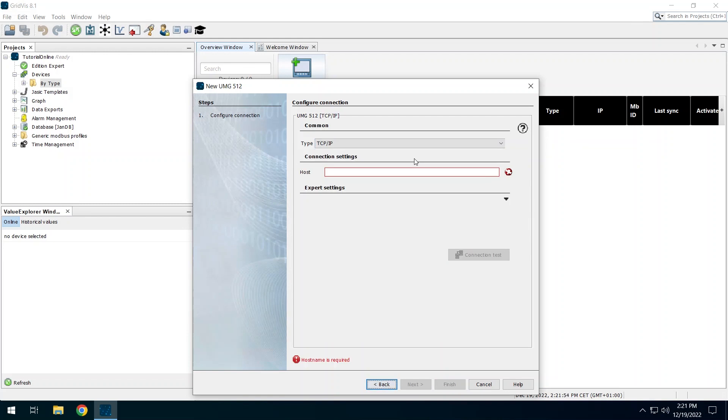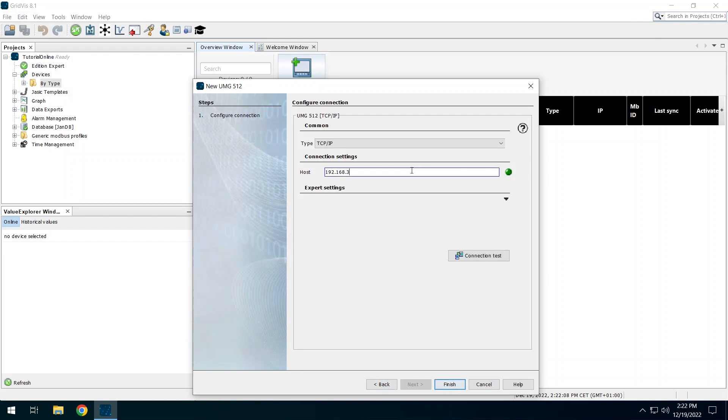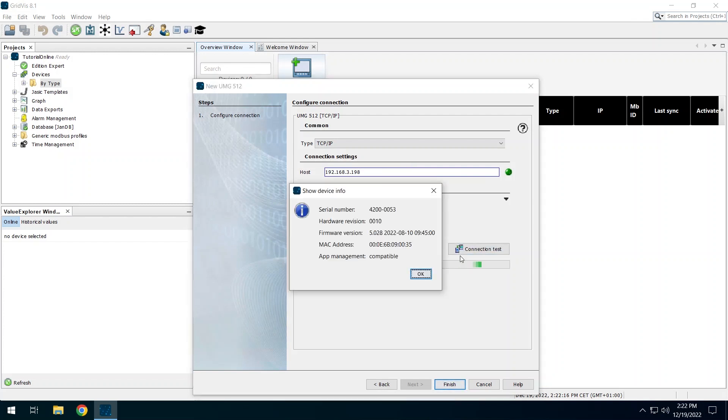Enter the IP address of the UMG512. Refer to the user manual to find out how to determine the IP address on the device. Click on Connection Test to check the IP address. The Gridvis now attempts to establish a connection to the specified address. The result is displayed in a pop-up window.